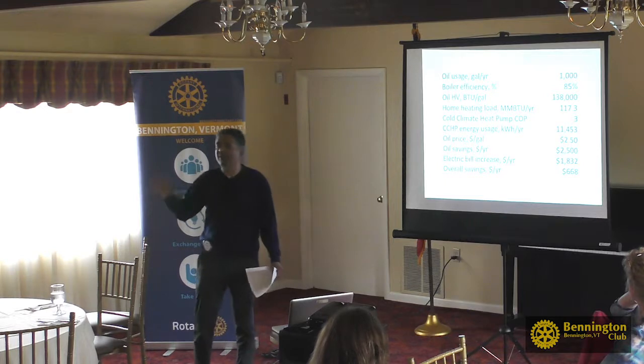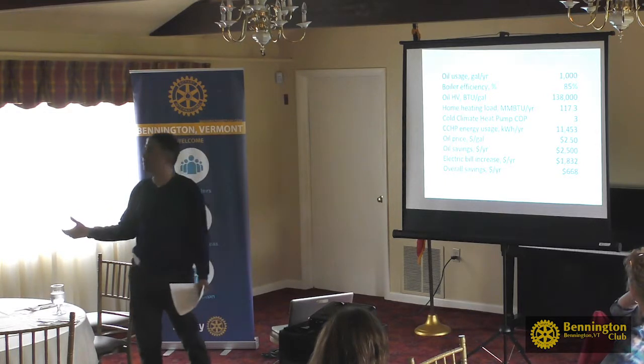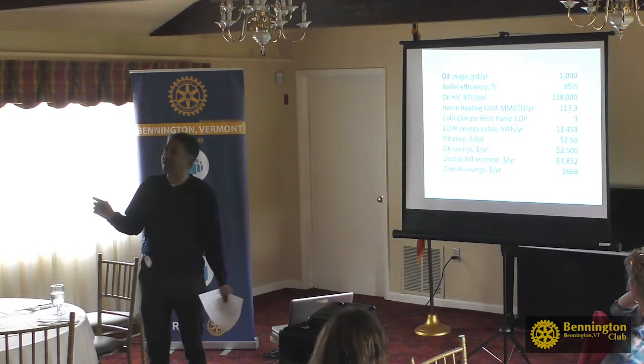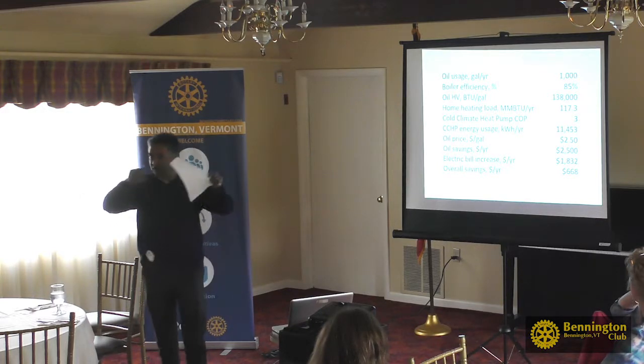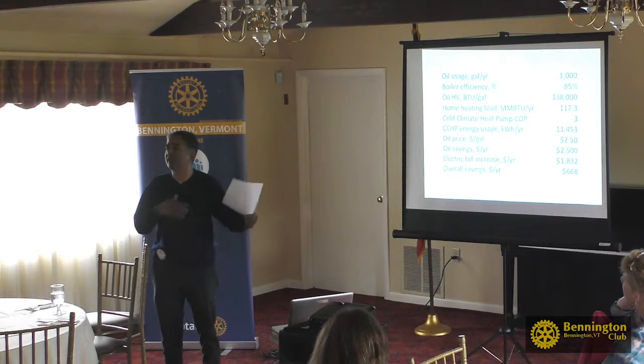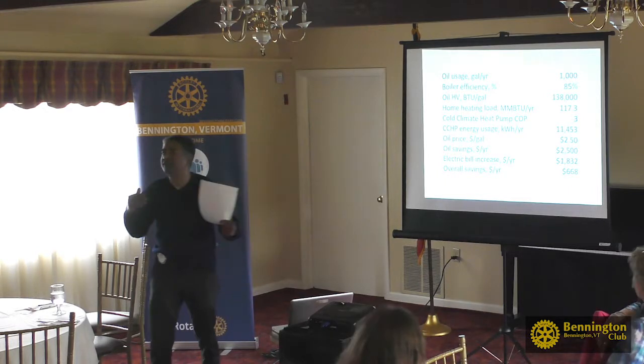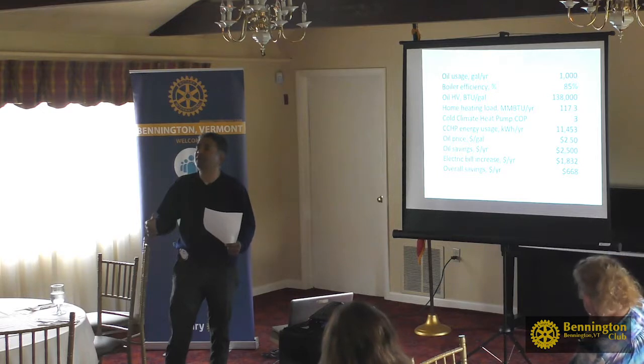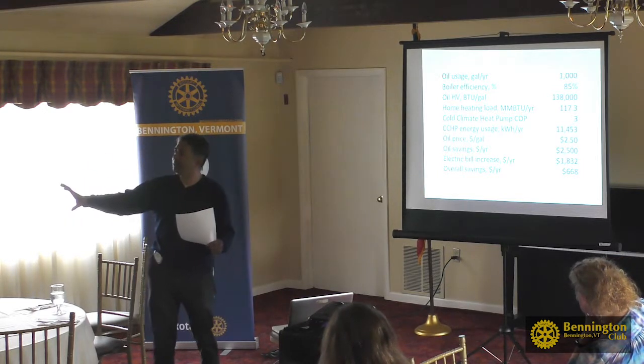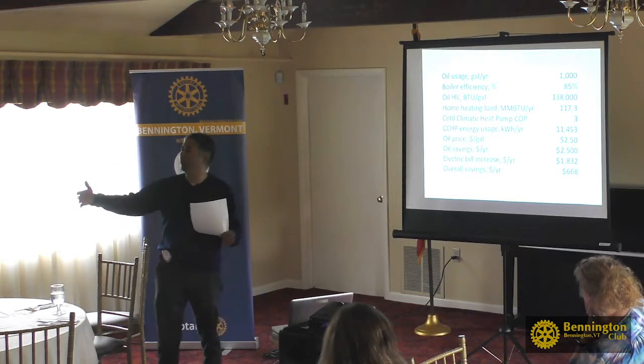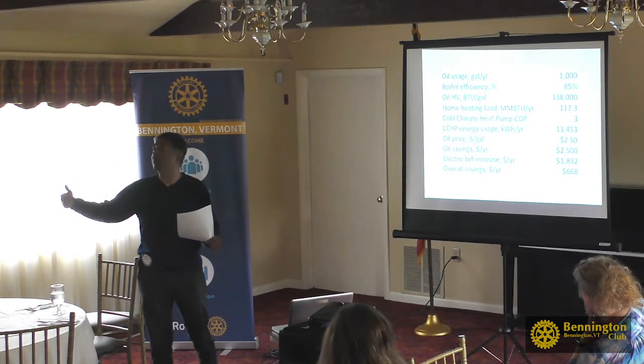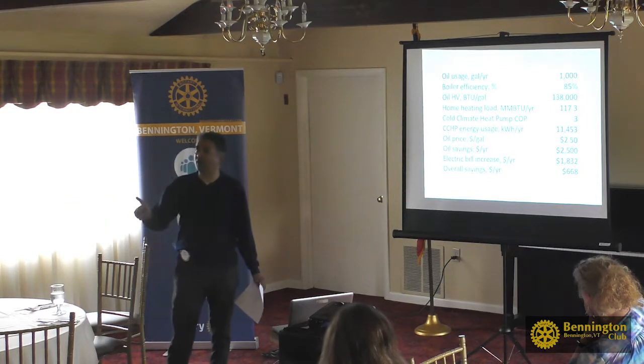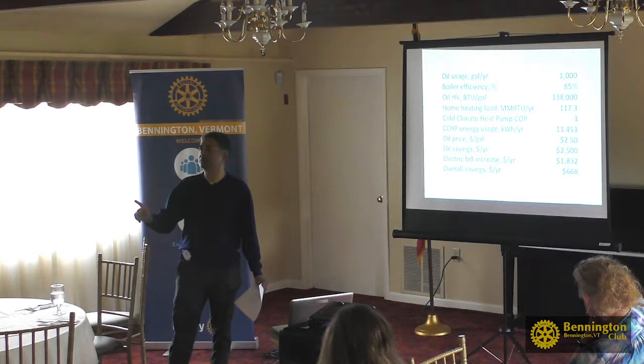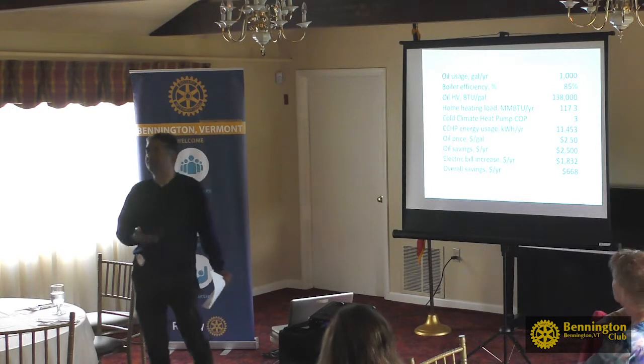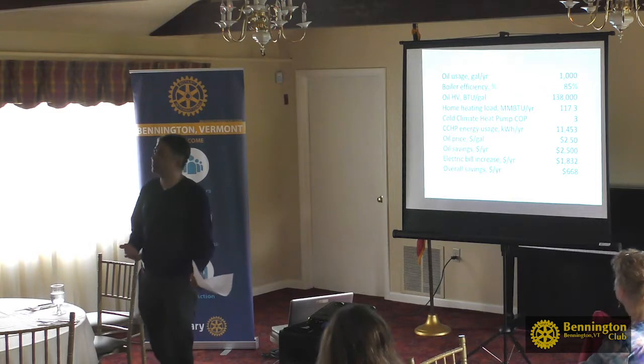So I mentioned to you that heat pumps are about 3 times more efficient than conventional units. That measure is something called COP, coefficient of performance. What that means is, remember we were talking about the fans and the compressors that run on electricity. How much electricity do you have to put into a heat pump relative to how much heat that it delivers? To deliver 3 kilowatt hours worth of heat, which is about 10,000 BTUs worth of heat, you have to put in 1 kilowatt hour of electricity. That's the COP, the measure of the efficiency of the unit.